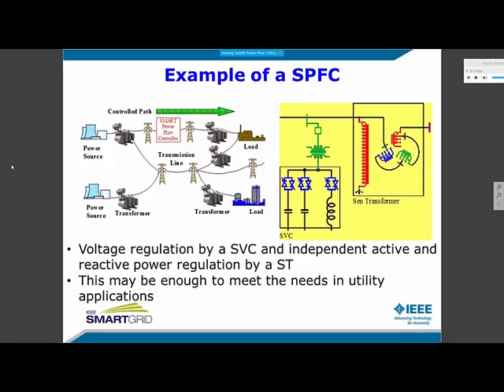Here is an example of a smart power flow controller that has to meet the functional requirements. If the voltage regulation is needed in addition to independent power flow control, particularly when the short circuit impedance at the point of compensation is high, a separate shunt-connected compensator may be used along with the transformer. This topology does not use any inverter to provide an independent PQ flow, which is contrary to the myth created in the last 2 decades.